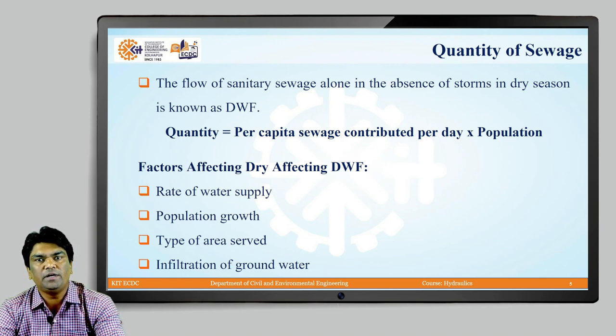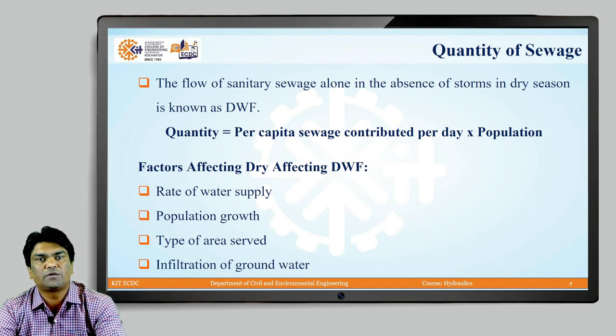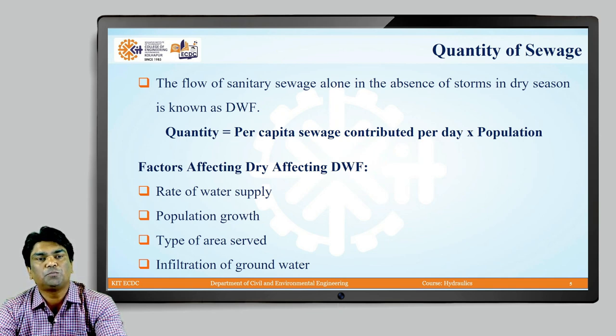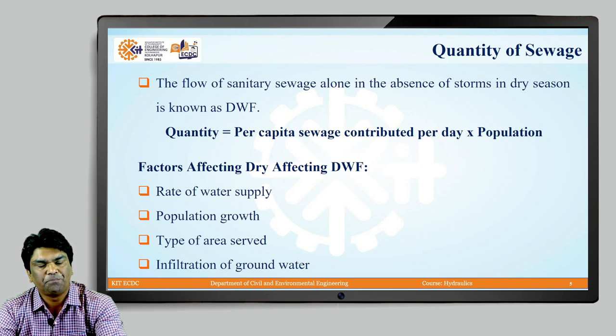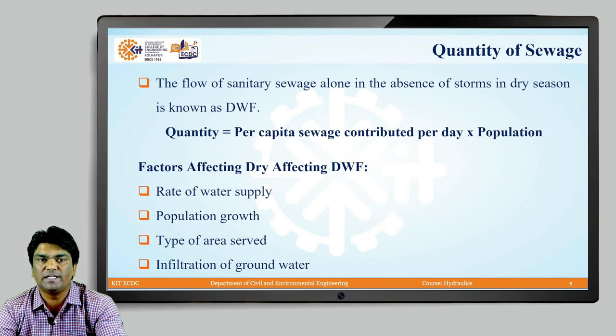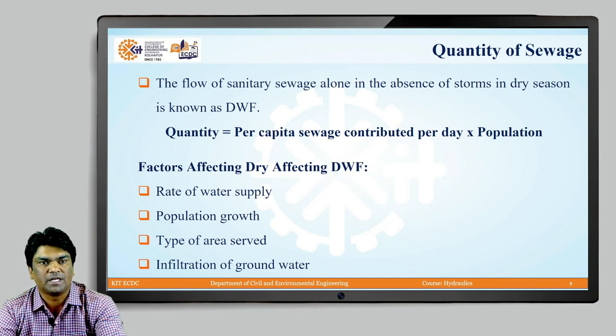The flow of sanitary sewage alone in the absence of storm in dry season is known as dry weather flow. The quantity of dry weather flow equals per capita sewage contributed per day multiplied by population. We first predict the population at the design period, find the average water demand, and then determine sewage quantity — since generally 70 to 80 percent of total water supplied is converted into sewage. Multiplying the per capita average by total population gives the total average sewage flow.